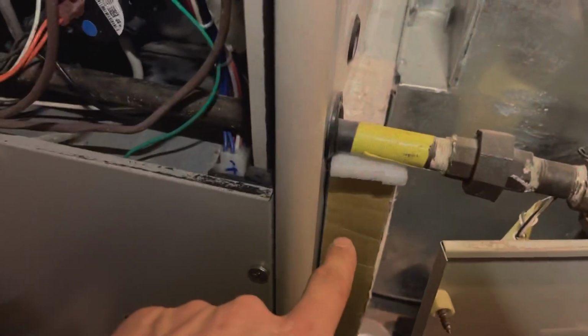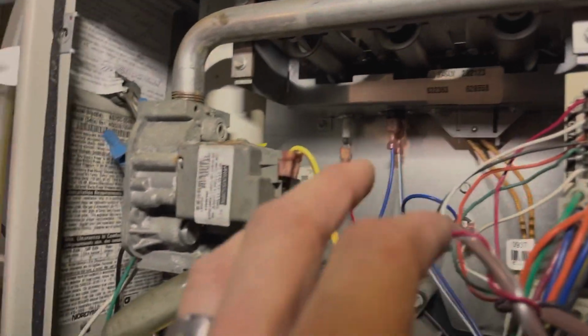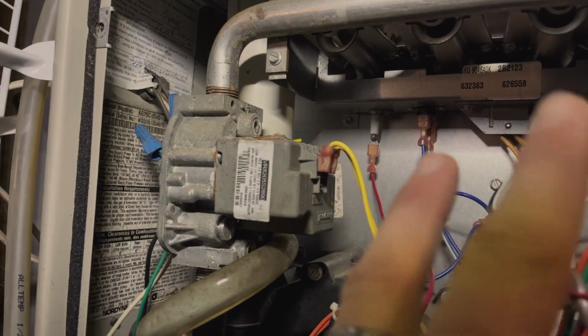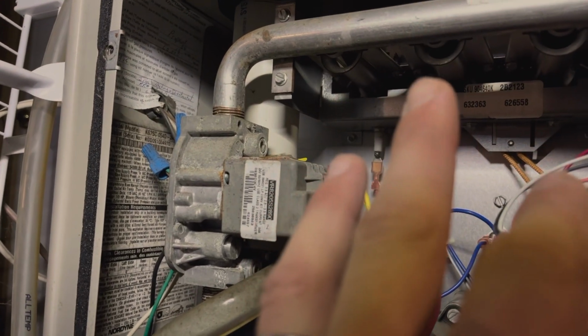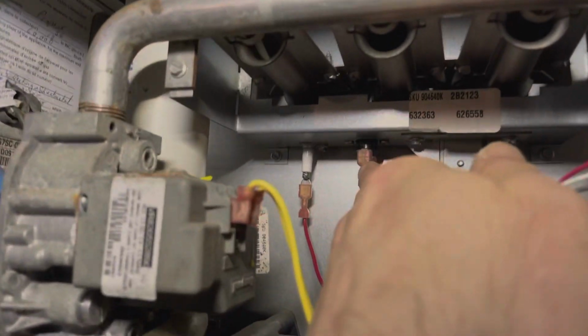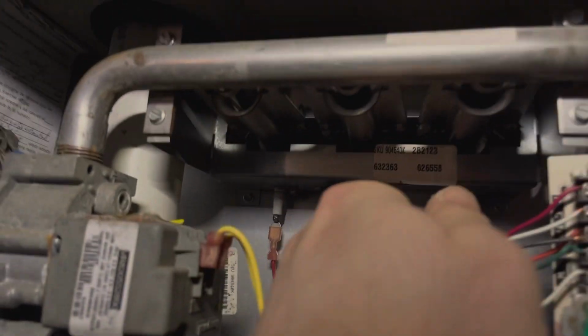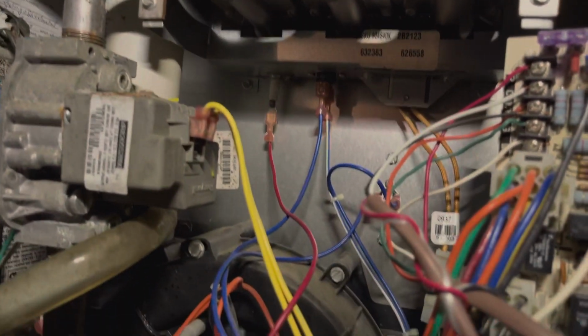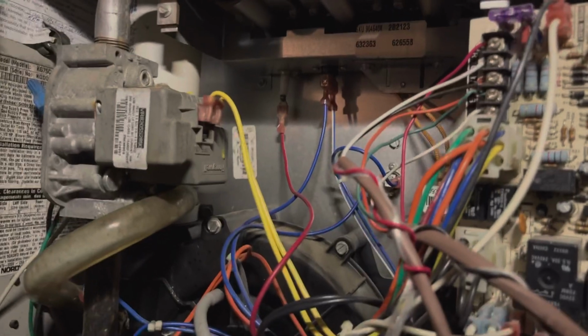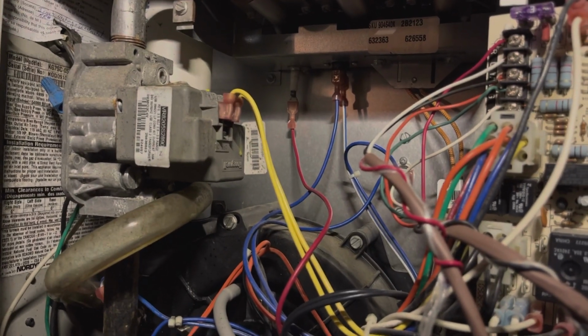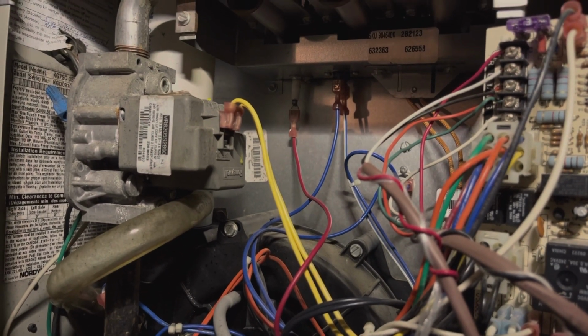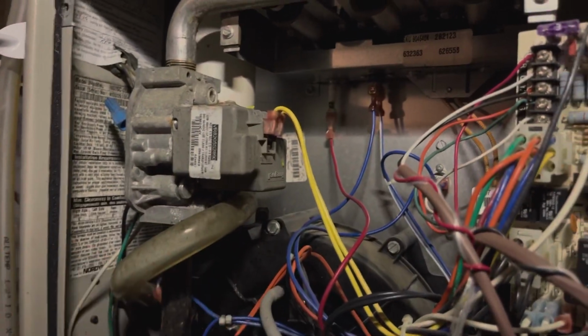Now, I had a fairly dirty furnace filter, so that could be the issue, and it was really cold out, so the combination of those things and the furnace running so hot so long, I'm thinking maybe they got too hot and it tripped that. We haven't had the issue since I clicked that and fixed it, diagnosed it. Very simple, but that could be your problem, or any of those other ones along the way.